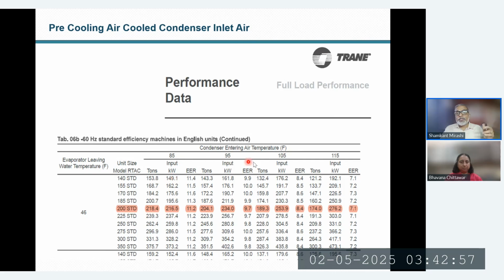When the ambient temperature starts going up, the same 200-ton chiller will deliver only 170 tons, almost 15-18% decrease in capacity. At the same time, the power consumption goes from 216 kilowatts to 276 kilowatts, almost 30% higher. So on one side capacity goes down, and on the other side power consumption goes up. This is a limitation.